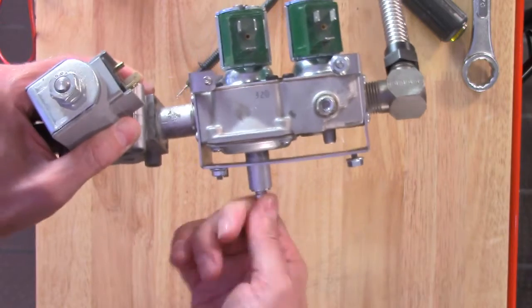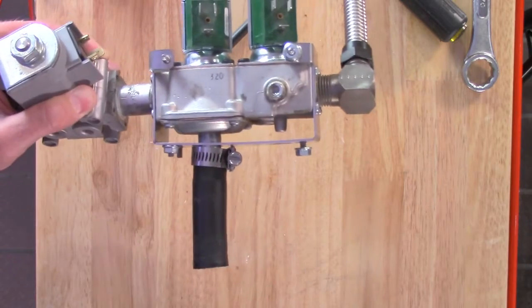We also mentioned if the location is constantly getting this covered with oil, then a field fix is to put a 5/8 hose on there with a hose clamp, right? And then if that's good to go, we want to check component-wise, make our voltage checks to see what type of voltage we have, if any, going out to our gas valve. If we have voltage going out to it, then we want to ohm out the coils on our gas valve to see if it's bad. And we showed how you can replace that. And also, if we don't have voltage going out of our control board, then it could be a faulty control board that needs to be replaced. Okay, so the gas valve solenoid we talked about, the gas valve itself, the control board.